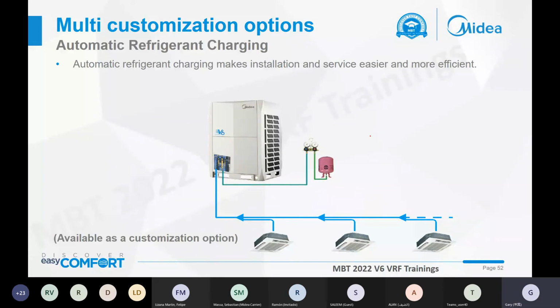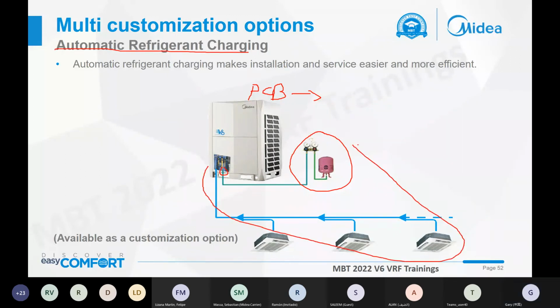So we applied the automatic refrigerant charge. This function is very useful and convenient. You only need to connect the refrigerant tank to the outdoor unit, and on the PCB of the outdoor unit set the automatic refrigerant charge. When the whole circuit runs normally and stably, which means the pressure has no change, the refrigerant charge is done, so you can quickly remove the refrigerant tank and tie the pipes. That is the whole process of the automatic refrigerant charge.